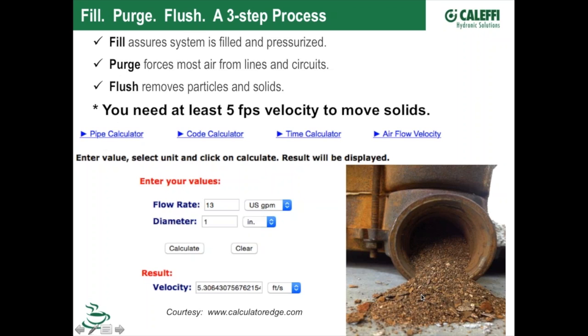In order to move heavy debris like this, sediment, dirt, solder balls or whatever might have settled down to the bottom, we need to have a pretty good velocity. We want to have about 5 feet per second or more velocity to flush that out. So the valve that you put in needs to be able to produce that amount of flow, or you're not going to be able to scrub any of this heavy metal out. How much flow do you need?